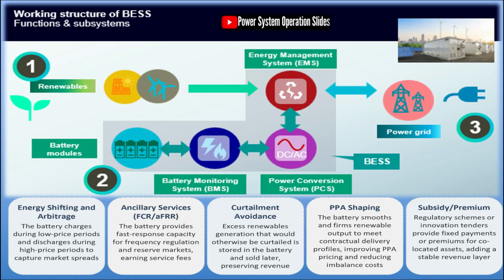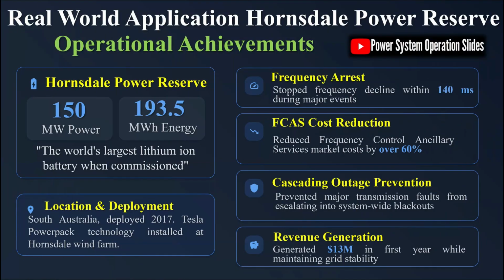The Hornsdale facility demonstrated unprecedented performance capabilities, arresting frequency decline within 140 milliseconds of a major disturbance, faster than any conventional generation resource could respond. This rapid response capability directly prevented cascading outages during major transmission faults, demonstrating the critical role that fast-acting storage can play in maintaining system stability.